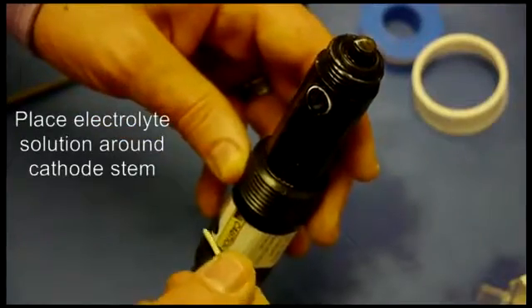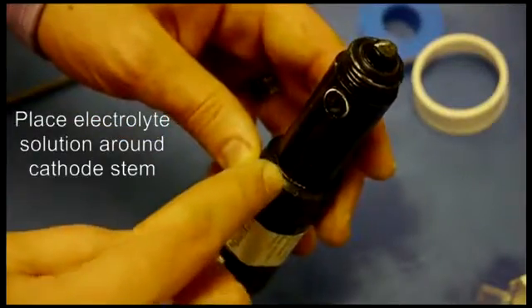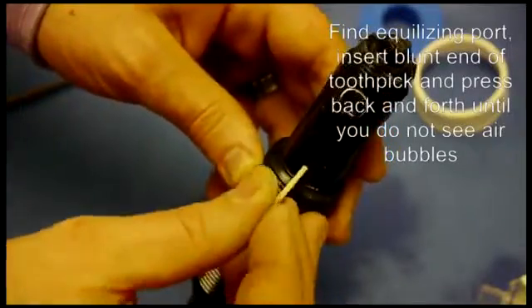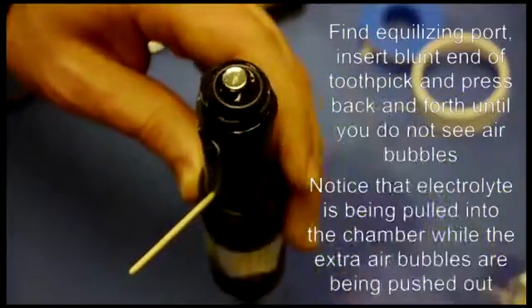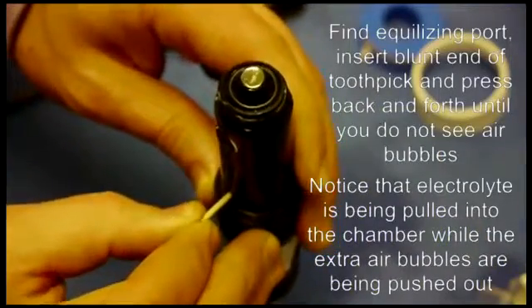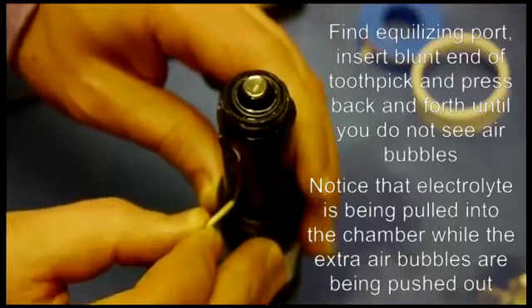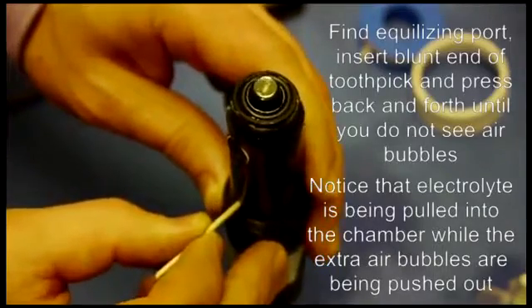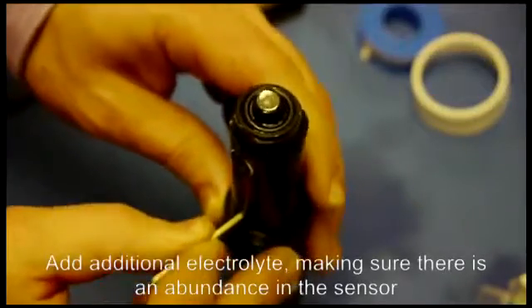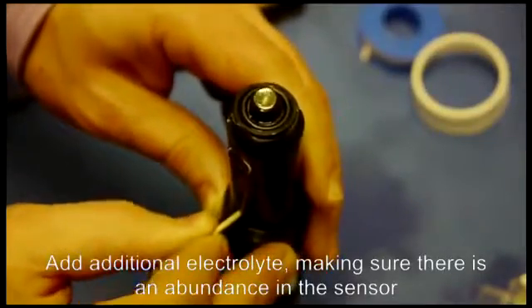Next find the pressure equalizing port, which is a small little hole above the threads. Take the flat end of your toothpick, place it inside, fill the solution on top of the cathode, and then press in to the equalizing port. See how I'm pushing the air out and it's getting replaced with the electrolyte solution? That's what we want. Do this several times until no more solution is left.